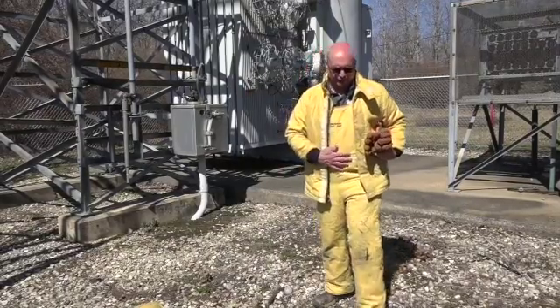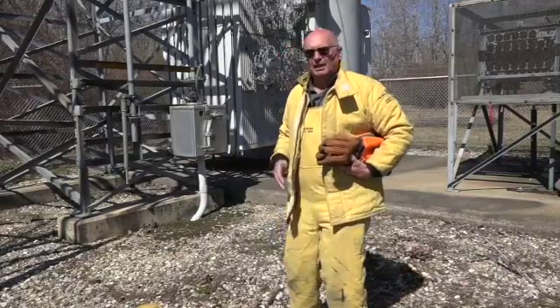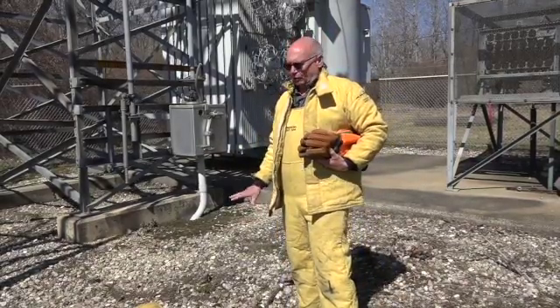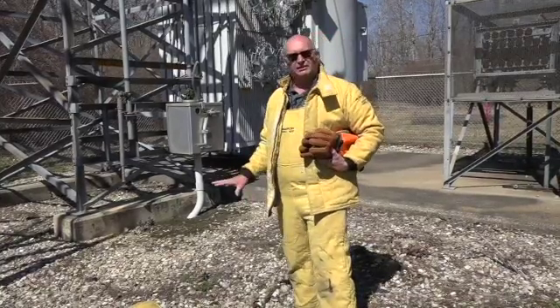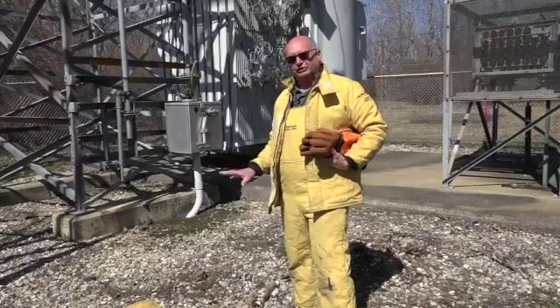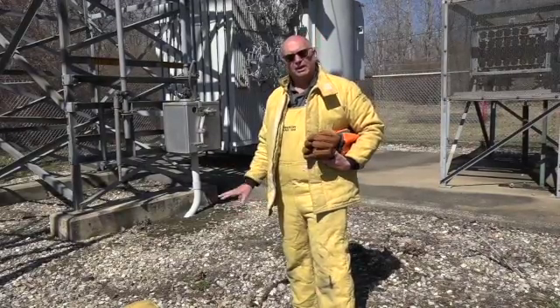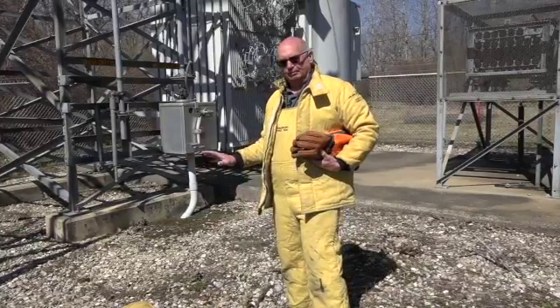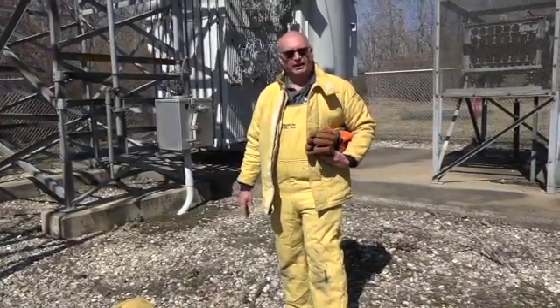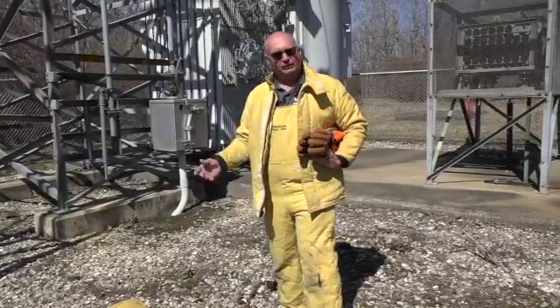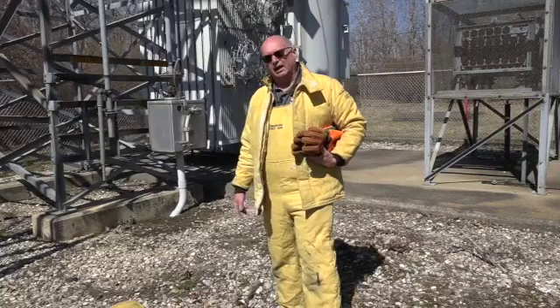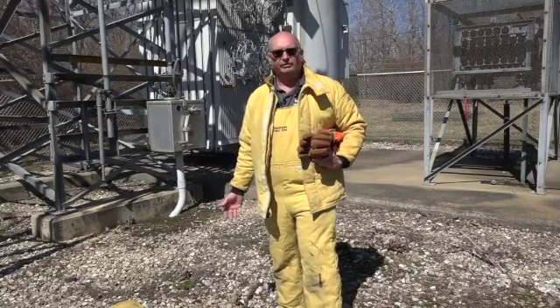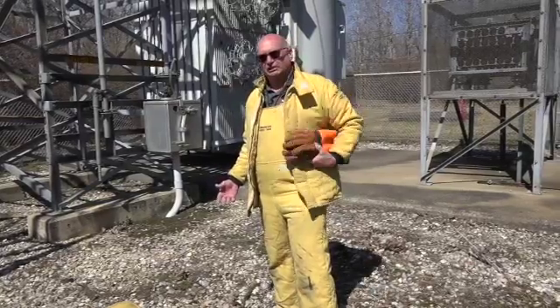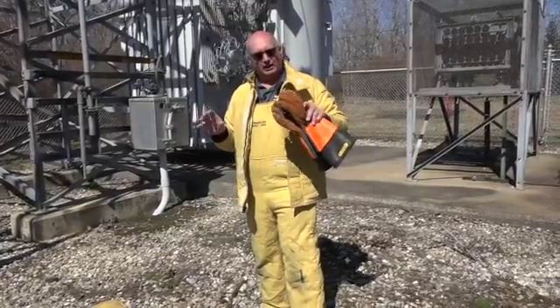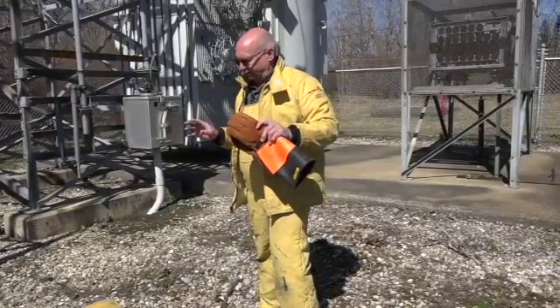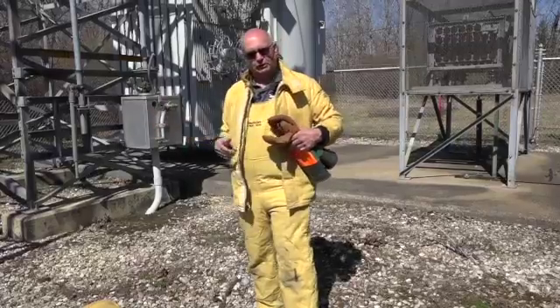What I'm wearing, the suit, is called an arc flash suit. We use it for testing, anytime we're testing lines to make sure they're off. And anytime you work with this type of equipment, you apply workers' grounds before you actually come in contact with any equipment. So you actually ground things out to make sure it's safe. You'll see a lot of utility companies actually work live. They'll have their electrical gloves on and handle the cables live, or they'll use the hot stick, which I'll show you shortly.